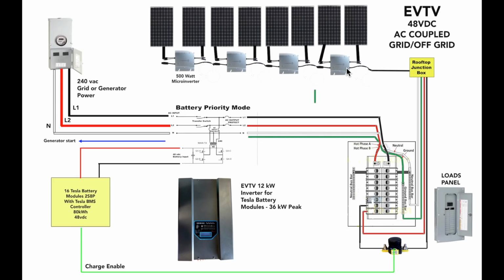And so we've done some experiments with it. We shut it down successfully without damage to equipment. But we don't want to do that very much. And so we've added a component here, a contactor, that disconnects one leg of the grid-tied solar. And in doing so, now they've lost their waveform and they shut down voluntarily because they think they've lost the grid. And so we can do that when the battery gets full, run off the batteries for a while, providing our loads, and run that battery down a little bit, say to 3.9 volts per cell, and then we will cut it back on. And with a 5-minute delay, these will come up again and start producing power.